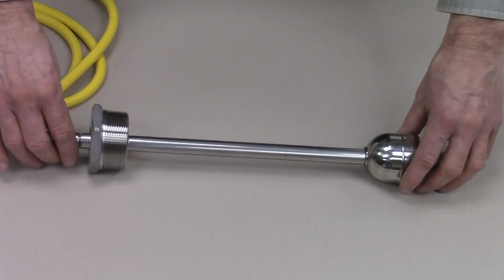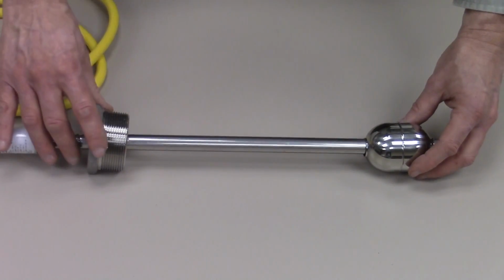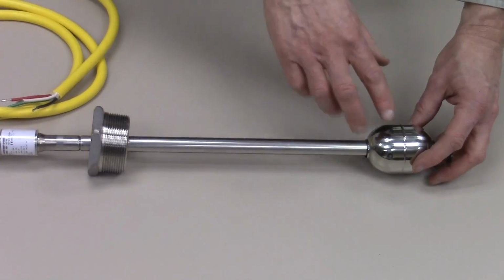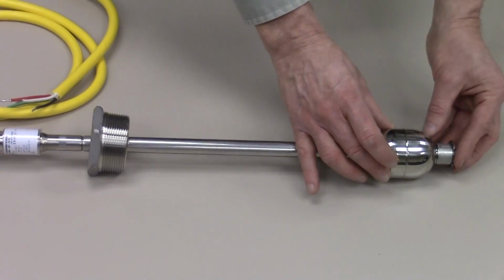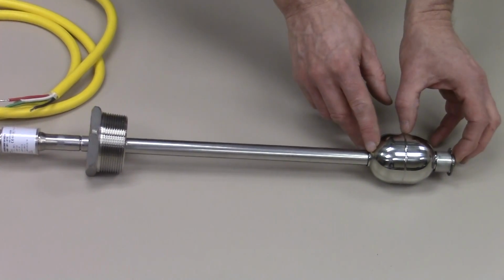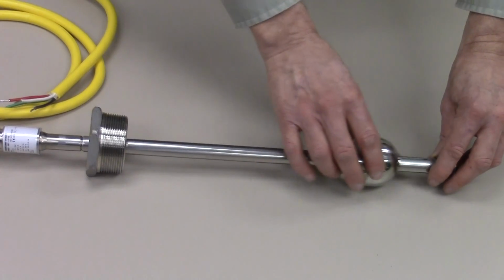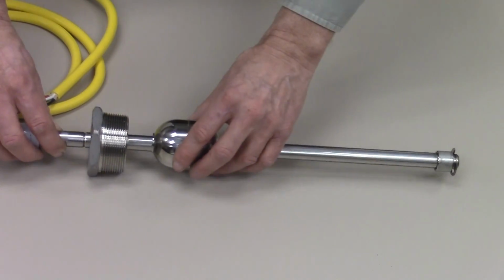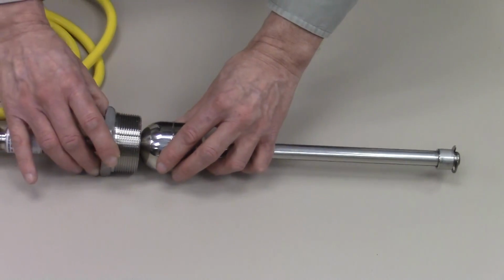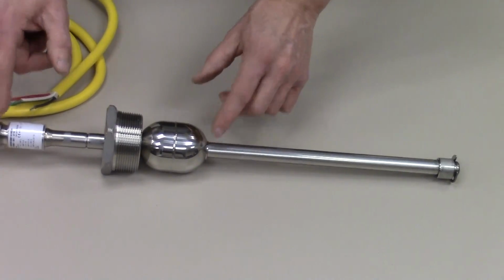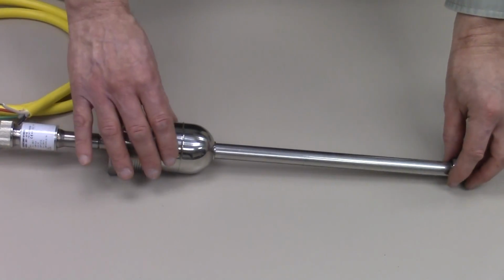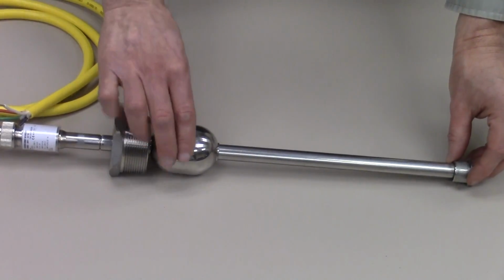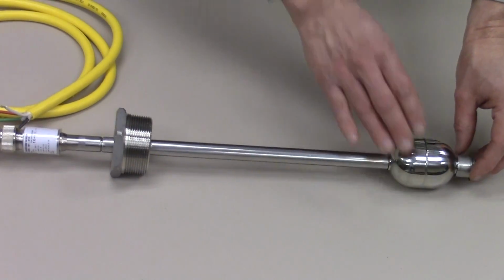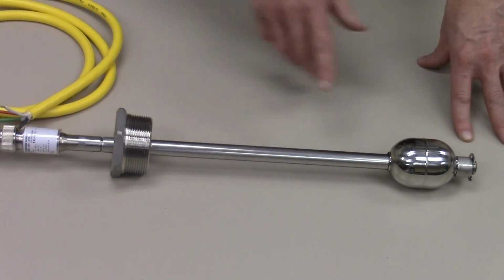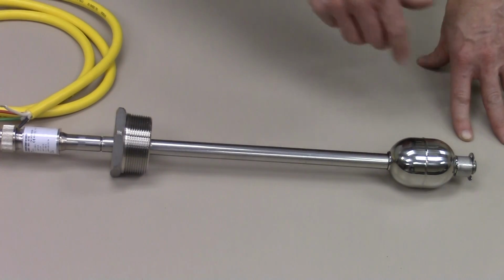The ProStik is shipped with the default 4 and 20 milliamps positioned as 4 milliamps at the bottom, 2 inches from the bottom of the probe, and 8 inches for your 20 milliamp position from the top of the connector. If the standard default 4 and 20 milliamp positions do not match your application, the product can be reprogrammed anywhere along the span of the unit.